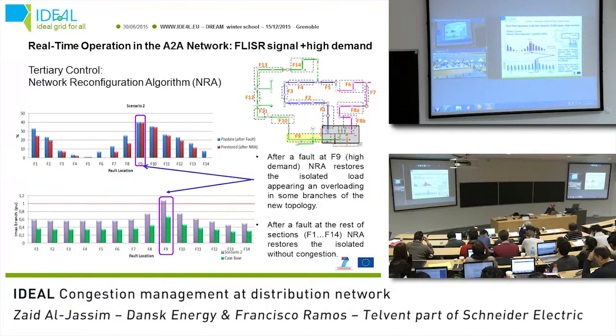And the figure below shows the gray bar, the loading of the lines of the network after the fault, and the green one was the loading of the network before the fault. You can see one is the maximum capacity of the line. So let's take F1 as an example. A fault has been simulated at F1, which you can find here. I don't know if you can see my pointer, but I'm pointing at F1. Yes, we can.